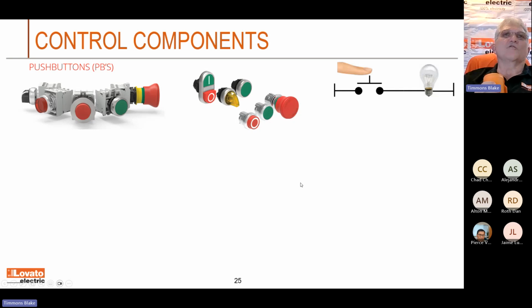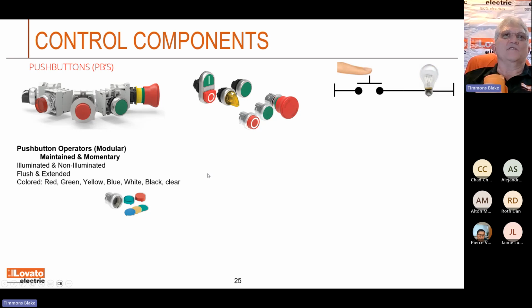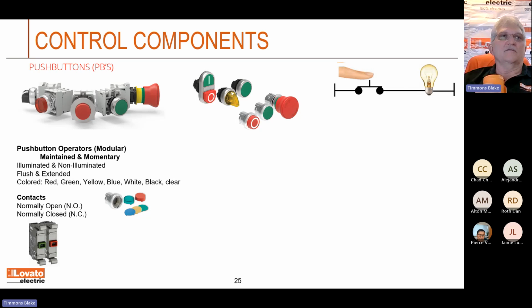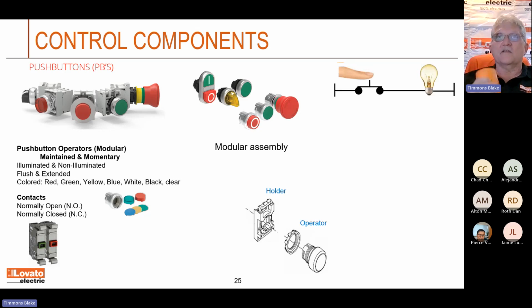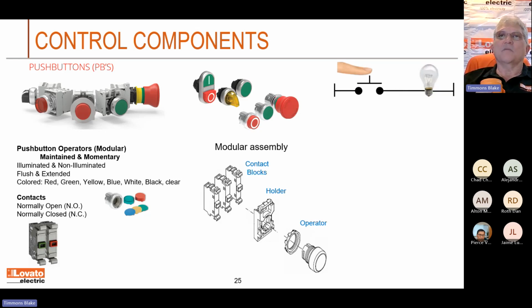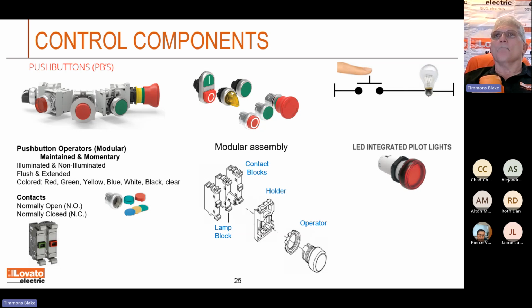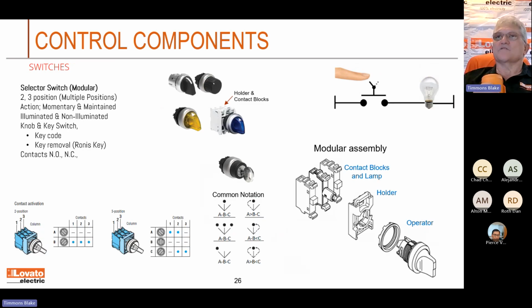Okay. And some of our control components you can just see are push buttons. A lot of people will buy these push buttons in different types. This is our modular series. Most of the companies out there all have this modular series, where you'll have an operator on the front. You'll have some contact blocks. We do it right here. Operator. You'll have a holder that kind of holds those things together against the operator. Then you'll have a set of contacts on the block. If it's illuminated, you'll have a lamp block in the middle. There's also another one called our monoblock, and these are nice, all one piece units. You got the LED and you got the contacts all right there built into one. Now that's a pilot light. Okay. Now here's our selector switches.